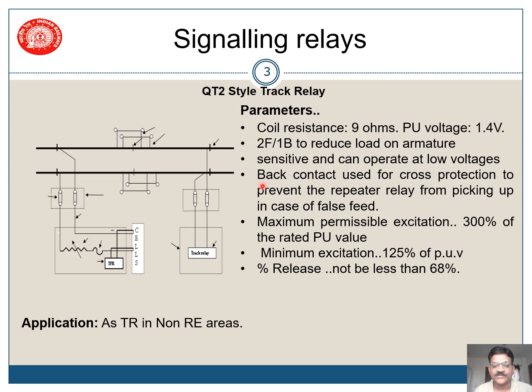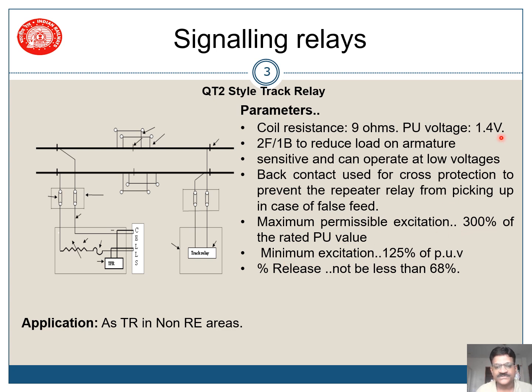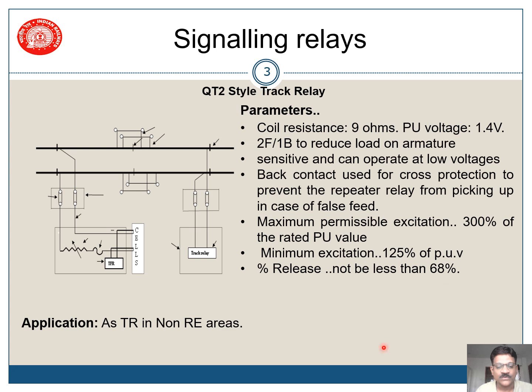Back contacts are used for cross protection to prevent the repeater relay from picking up in case of false feed — this is for failsafe operation. The maximum excitation permitted is 300 percent of the rated pickup value, which is 1.4 volts. The minimum excitation is 125 percent of the rated pickup value. The drop-away percentage shall not be less than 68 percent. This relay is to be used only as a track relay in non-RE areas.